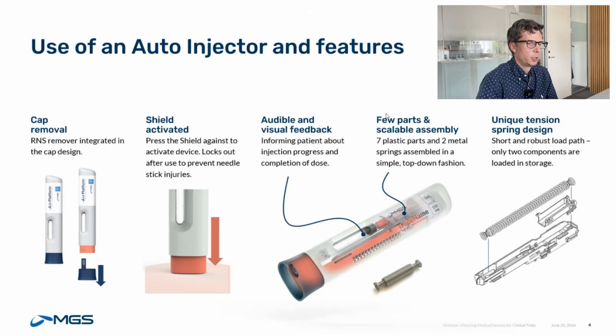The unique part about this auto-injector compared to other auto-injectors is that it uses a tension spring rather than a compression spring, and it's loaded between 2 parts and that's interlocked. But let's go directly to the framework.